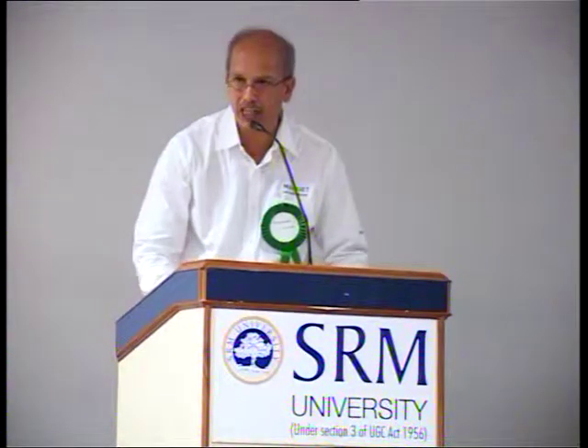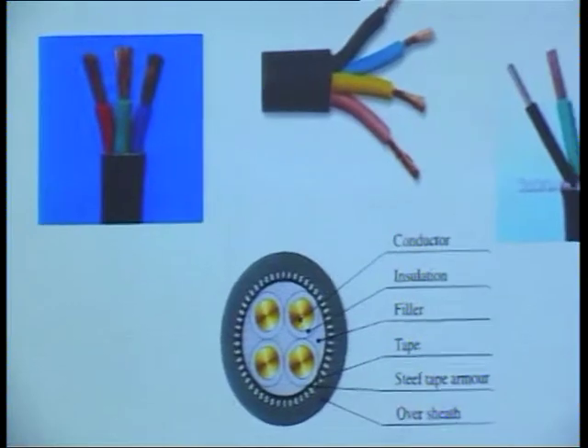Now, in your house or in the equipment which you normally handle, most of these equipments are working on 5 ampere connections, or at the most at your house you might have seen equipment working on a 15 ampere plug top. That is the maximum wire connection you have seen. But when it comes to biomedical engineering equipment, you will find equipment which sometimes needs a 100 kVA supply, or much more than that. For example, equipment like MRI, CT scanners or cath labs, their generators actually consume a lot of power.